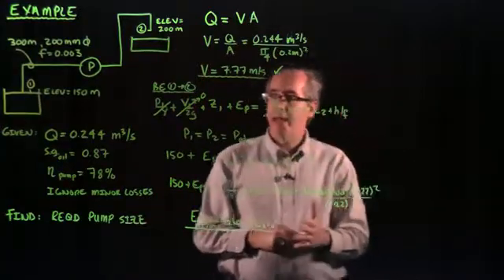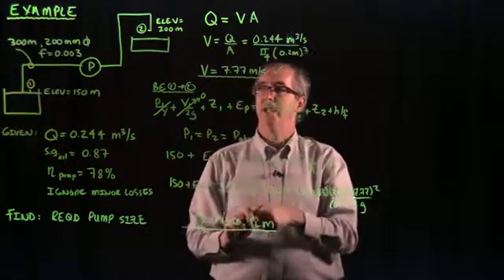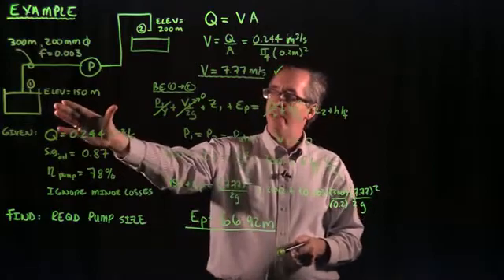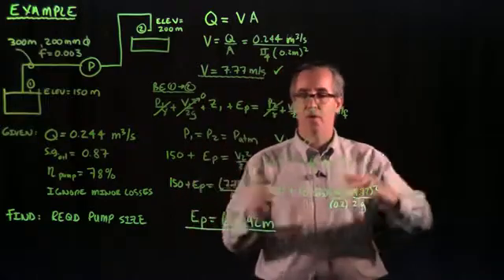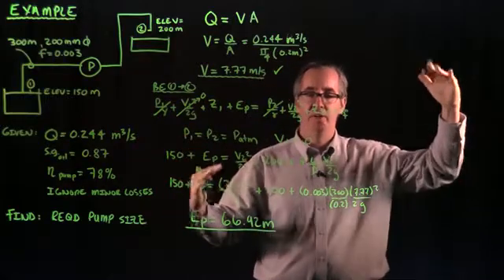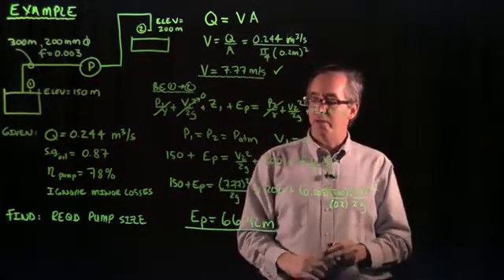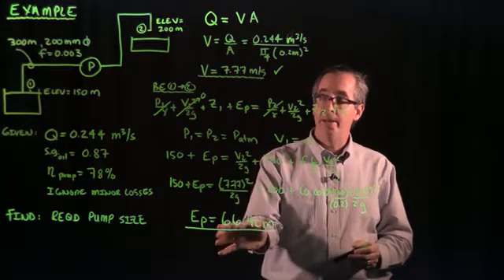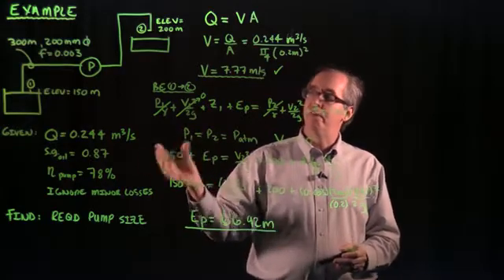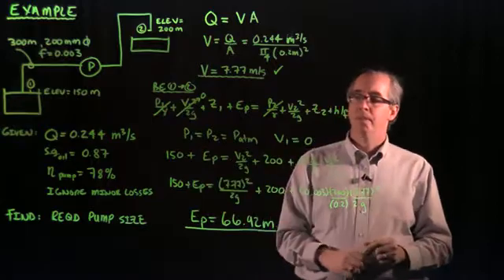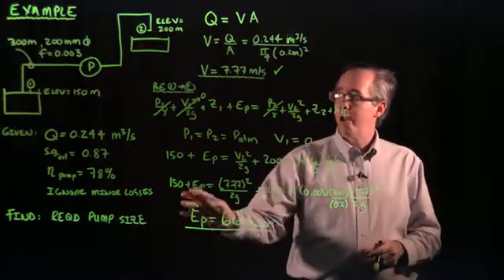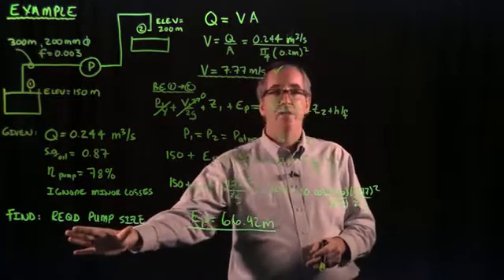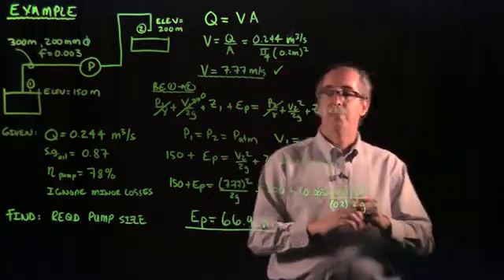So what that's telling us is this. Remember, the pump head is more than just the elevation change. The elevation change is going from 150 to 200 meters. There's 50 meters of elevation that the pump has to overcome. But there's also another 16.9 meters of friction losses that the pump has to overcome as well. Now, we've got the pump head, but what we're actually looking for in this problem is to size the pump. So we have one more step with this.